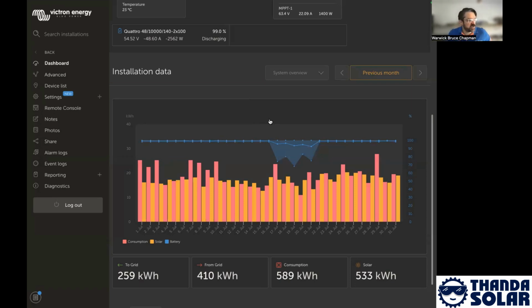Only recently, Victron introduced the RS family of products, and soon the HS, the high voltage, high frequency, three-phase products that are on the way. And those have a different, more modern topology where they use high frequency, high voltage switching electronics to transform DC into AC, right? And the conventional wisdom over the years has been that a tough transformer-based solution is more robust in the long run. But you know, Victron has waited, bided its time, and come up with a design that's extremely efficient.